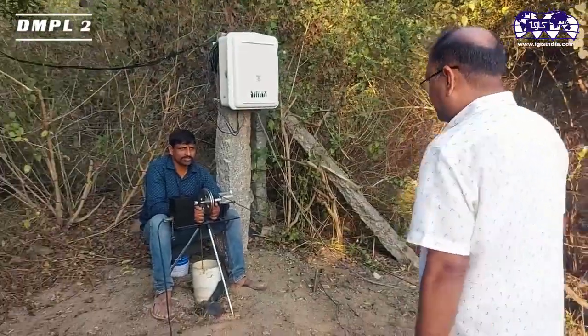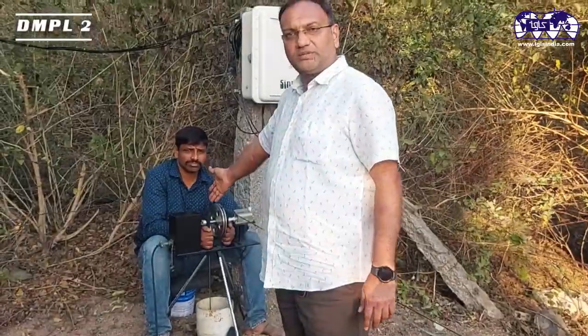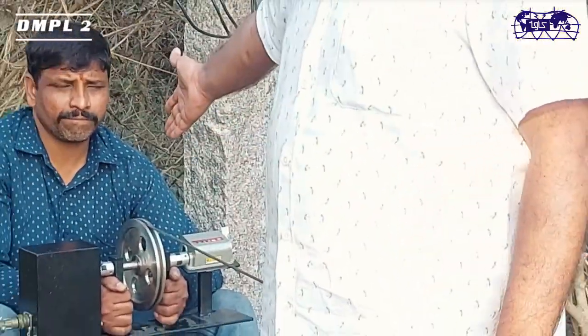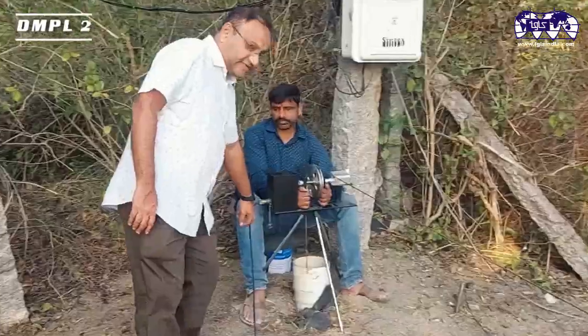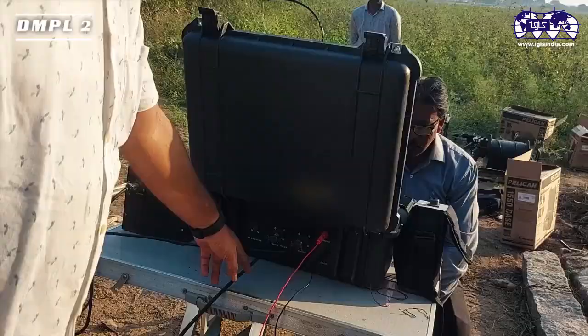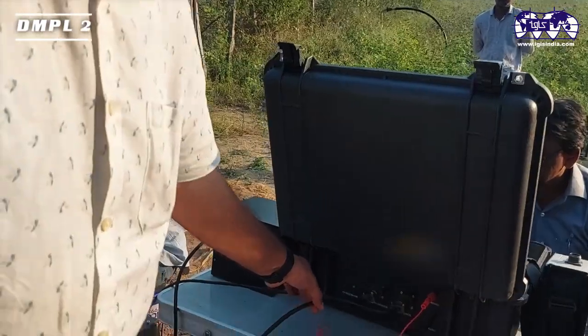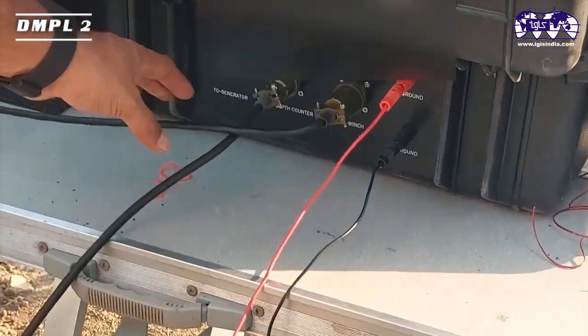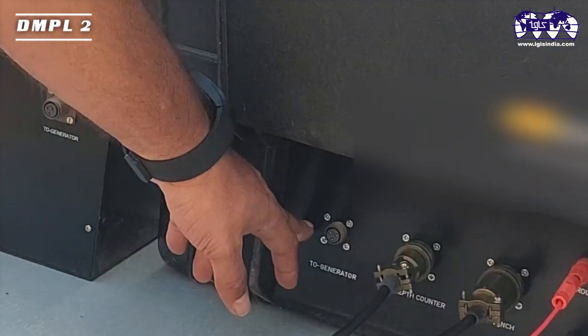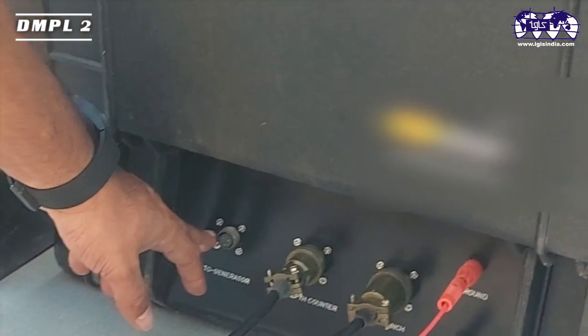Here, as mentioned, we have lowered the probe up to the bottom of the depth, 48.4 meters, and here we have connected the depth encoder to the machine. This is the counter, and this connection is the winch. Here we have an option for generator as well.